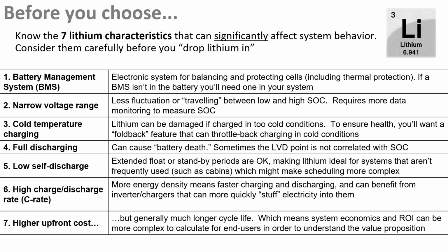Full discharging, again, that's something you'll see with different manufacturers in terms of how they rate it. You'll notice the cycle life that Nate quoted earlier, the 4,000 cycles, was at 80% depth of discharge. And that's typically where you want to have your LVD set point for any DC or AC loads set on your charge controller or your inverter, because you don't want to discharge much below that.